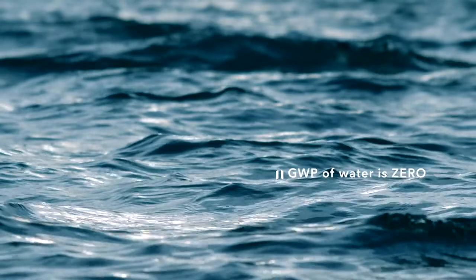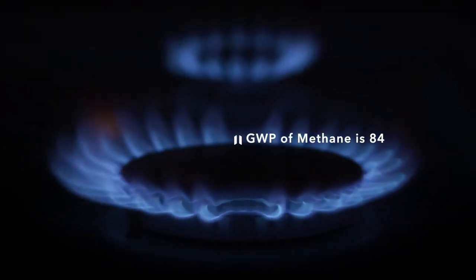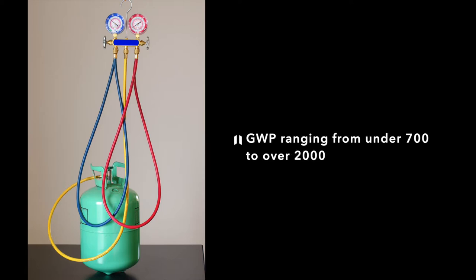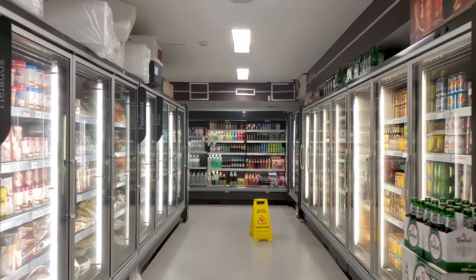Warming potential, or GWP, is the amount of heat absorbed by any greenhouse gas in the atmosphere as a multiple of the amount of heat absorbed by the same mass of carbon dioxide, which has a GWP of 1. The GWP of water is 0. The GWP of methane, the main ingredient in natural gas, is 84. Refrigerants, however, have a range of GWP ranging from over 2,000 to under 700, some of which are flammable, especially with the addition of required lubricants.